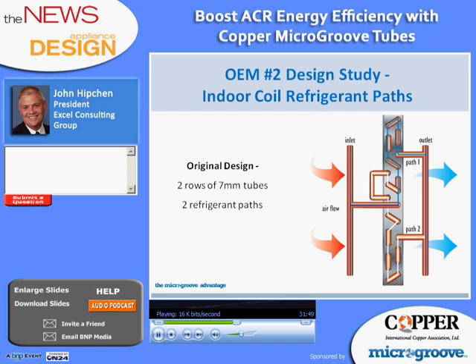Here's the tube circuit diagram for the original design of the indoor coil for OEM number 2. And we can see an already fairly unrestricted design with 2 paths. Note the inlet on the left and outlet on the right. It gives us refrigerant flow in the same direction as air.